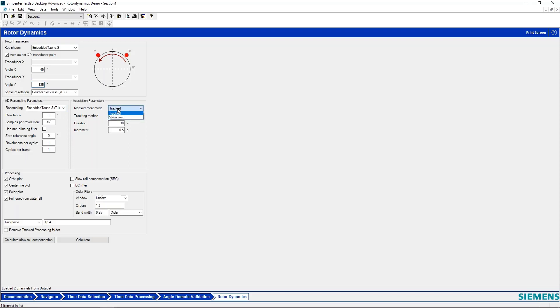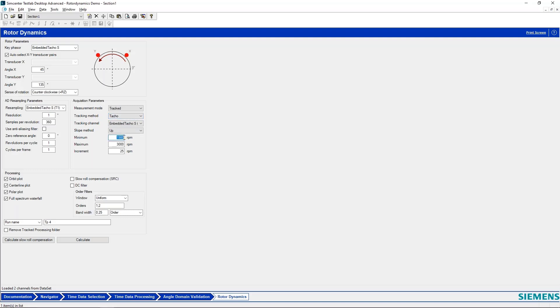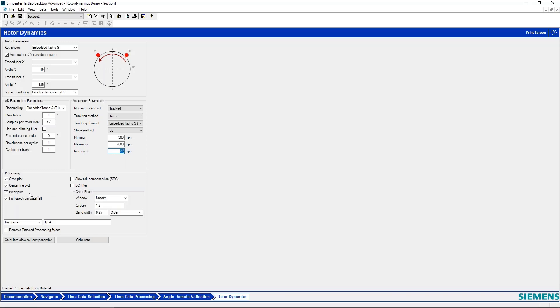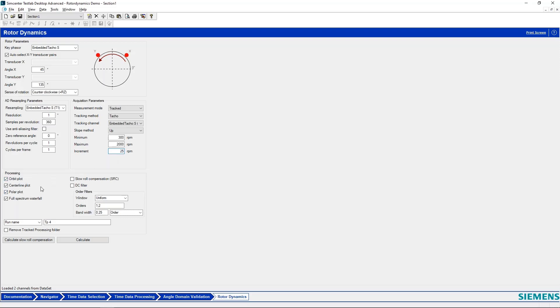I can take a measurement. I might say I want to perform analysis on that run-up, so I'm going to use my tacho as my tracking channel. And then I'll say I want to analyze this from 300 RPM to 2000 RPM, and I'll have an RPM increment of every 25 RPM. So basically for things like my orbit plot, my centerline plot, and my polar plot, my full spectrum waterfall, I'll be calculating an orbit every 25 RPM, a point on the polar plot every 25 RPM, and so on.